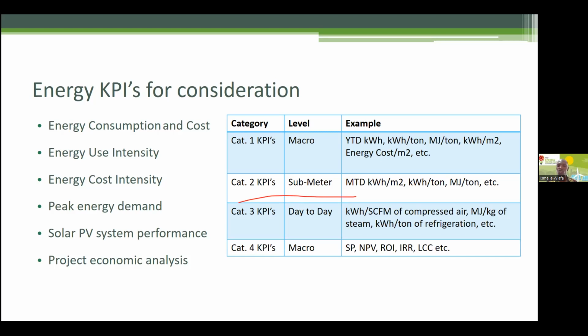For compressed air systems in industry, you need to monitor energy use per specific CFM or airflow for the system. For chillers or refrigeration units, you need to evaluate energy use per ton so you can compare to benchmark values and improve.